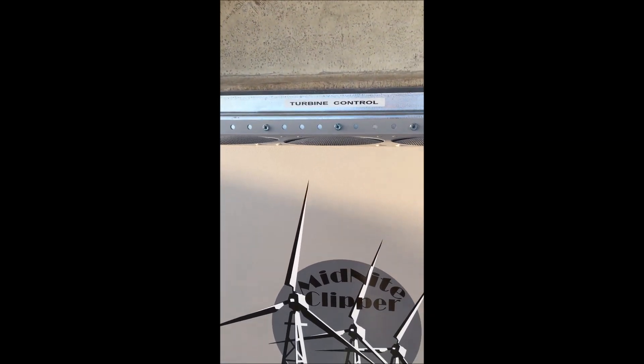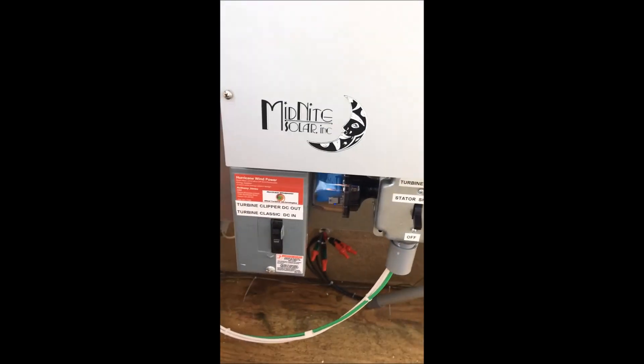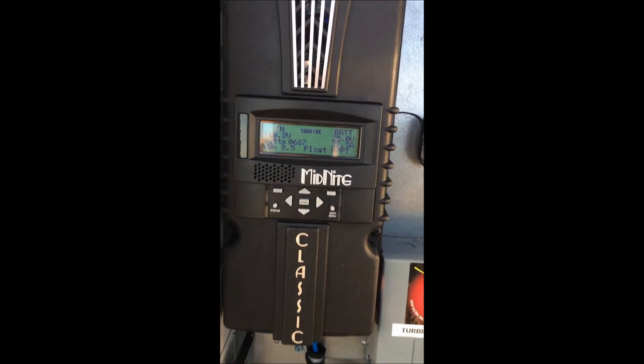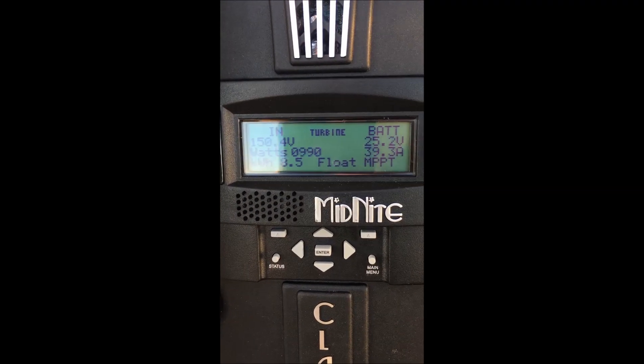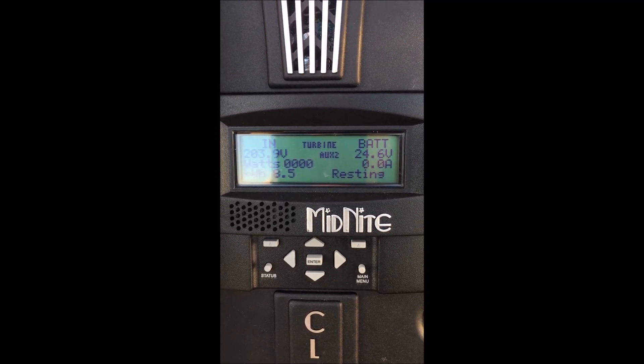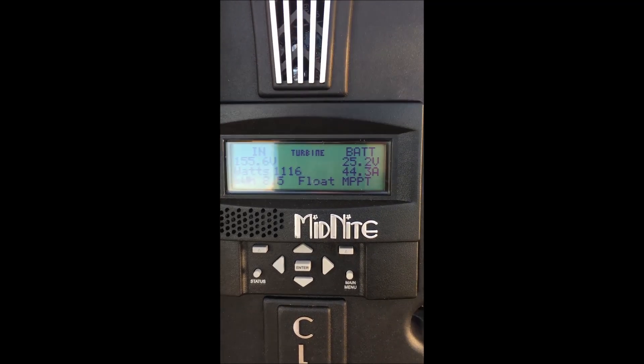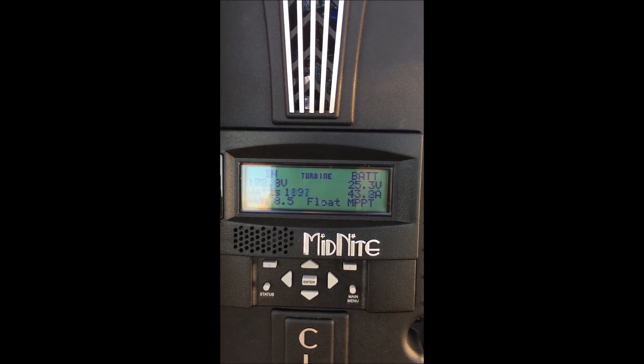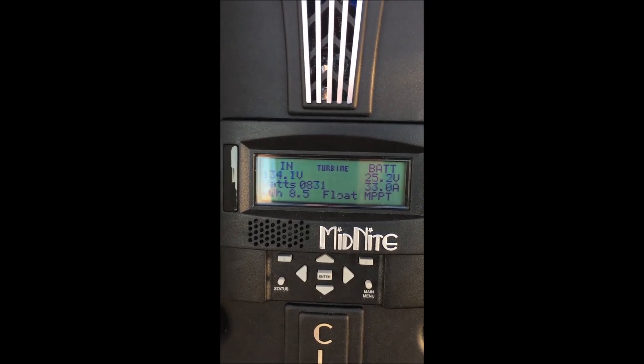Our lightning is doing its thing. Inside the cabinet the MidNite Clipper's fans are running and we've got some warm air coming out of the top, which tells me that pulse width modulation is happening. Up here is the turbine controller — you can see the AUX2 kicking in, sending the pulse back to the turbine to slow it down just a little bit: 43 amps, 165 volts.